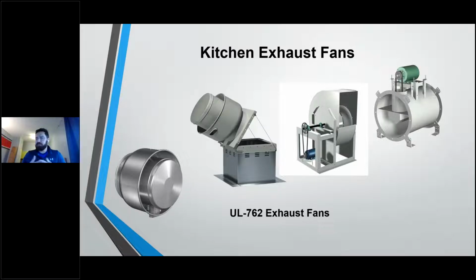The final type of exhaust fan that we're going to see in a standard kitchen ventilation system would be an inline exhaust fan with the motor removed from the airstream for UL 762. In the last part of this presentation, we're going to touch on pollution control units as well, which is another type of exhaust fan, but it's not really your traditional UL 762 exhaust fan. It actually has a different rating to it.